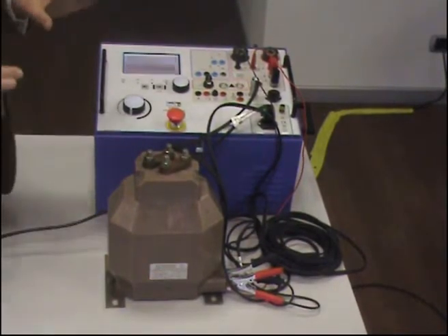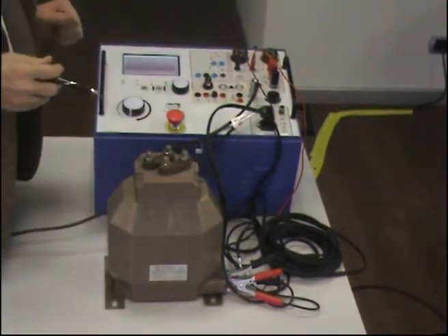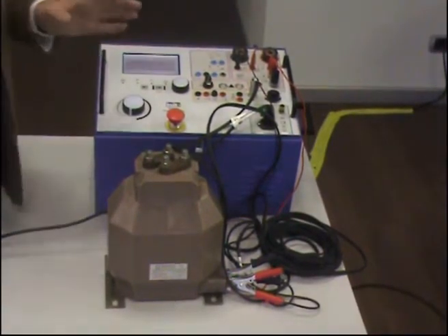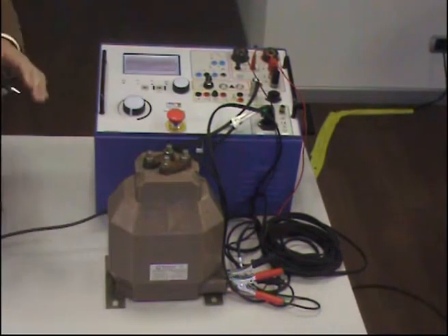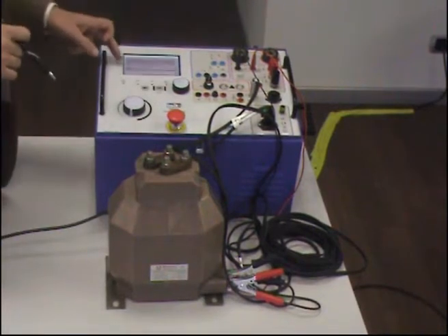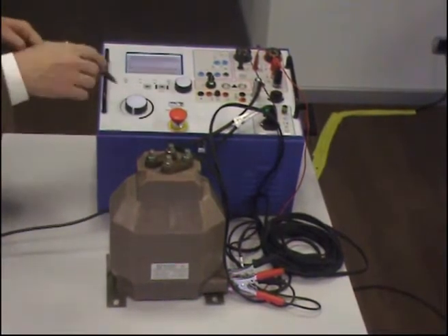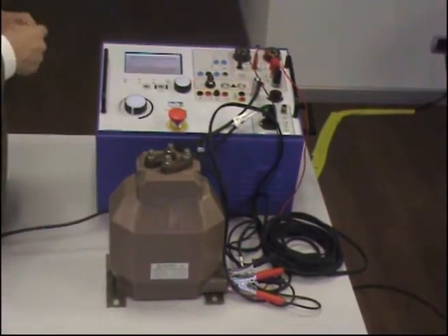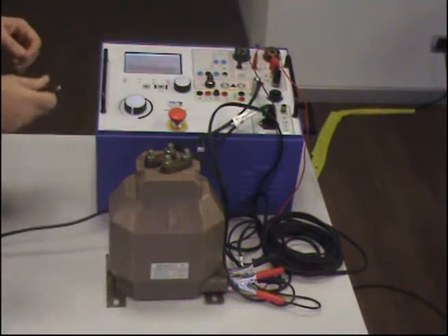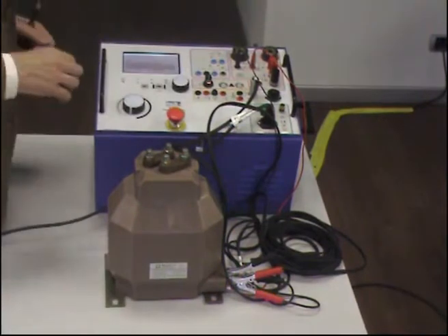Generally speaking, you have to take real care when you are performing this test. Why? Because we are generating a DC current, and by definition the DC current is saturating your transformer. It is saturated. So, after this test, it is absolutely advisable to perform another test with AC, so that you remove these remnants that are surely there. The other thing is that according to the dimension of your current transformer, there could be a problem that you can be facing.